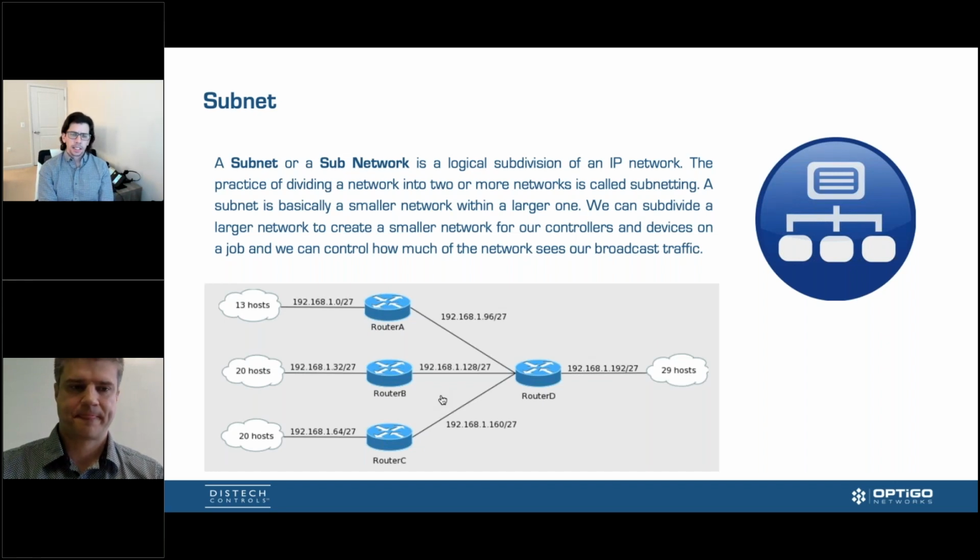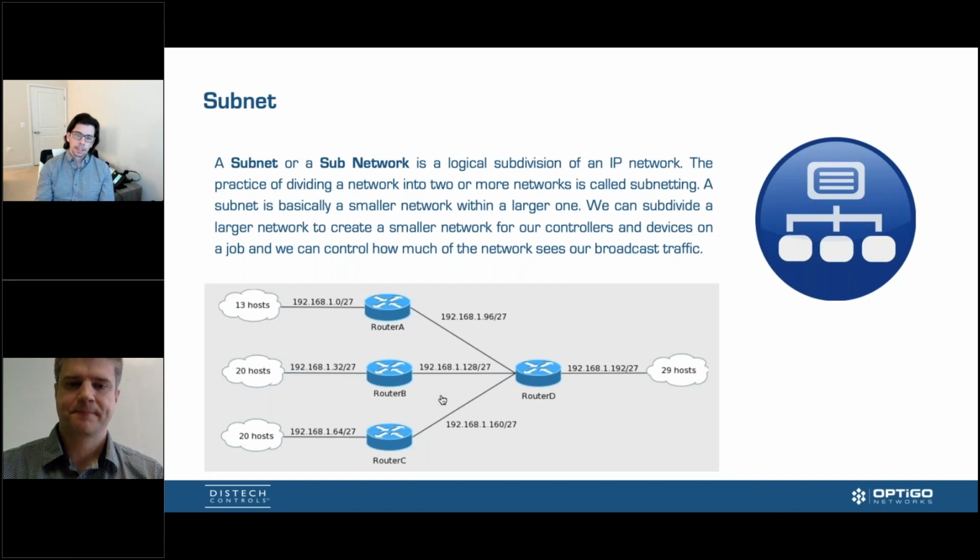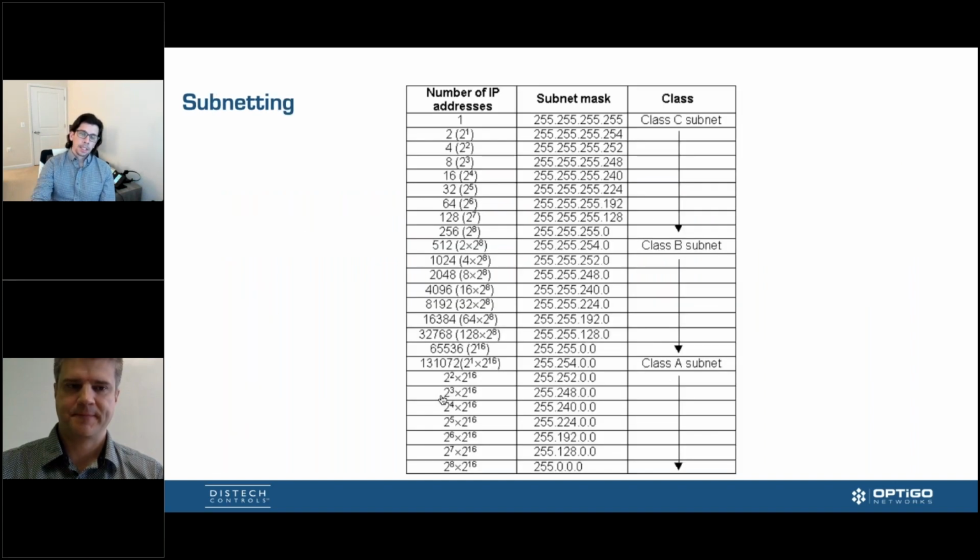And most often, this will be something you're handed, because somebody may say, well, you have 3 controllers, so I'm going to give you a 240 subnet. So we can keep going forward with that. But subnets, unlike VLANs, don't necessarily block broadcast traffic. So there is a difference there. On a small job it's not the same as a VLAN, where VLANs have better inherent security. There are a lot more differences than that. But keep in mind, doing just a different subnet is not the same at all as doing a different VLAN. Subnets are a better way of just logically grouping stuff, not security. So that's important to understand.